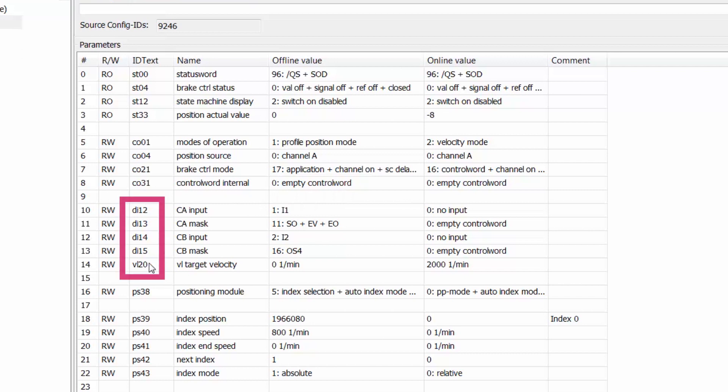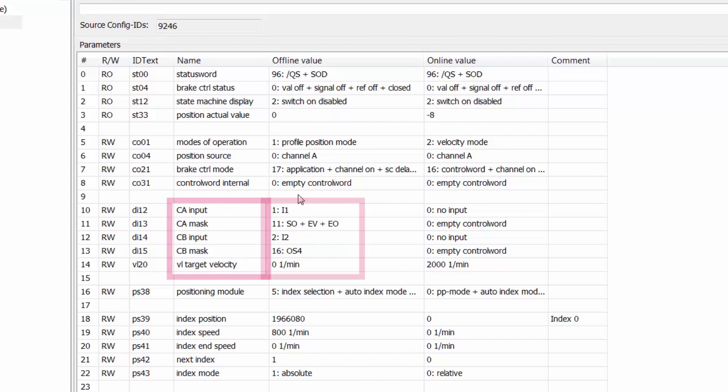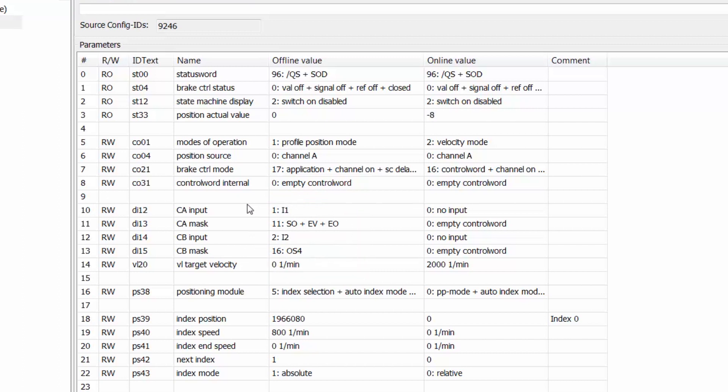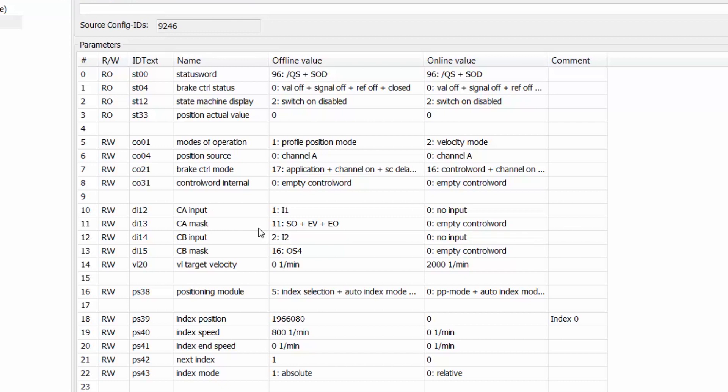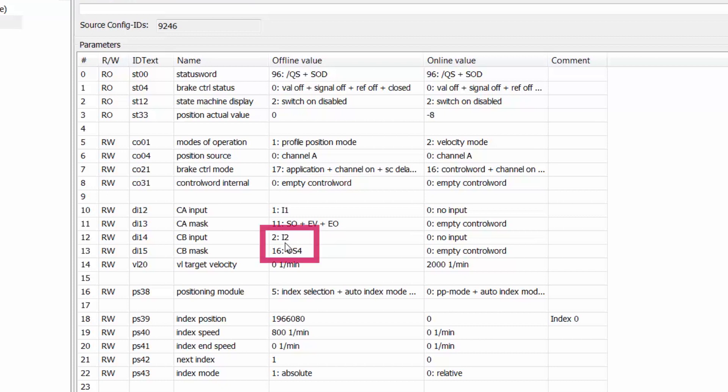Looking at the DI parameters we have our CA input, CA mask, CB input, and CB mask. So these four input parameters are inputs and masks for the control word. So since we are not using a PLC in this case we will actually use digital inputs, specifically digital input 1 and digital input 2 as shown here in the CA and CB inputs to control aspects of our control word to enable the drive for operation and positioning. So input 1 will switch the drive on, enable the voltage, and enable operation for the drive to move. Activating digital input 2 will serve as our positioning command as that is operation specific input 4.